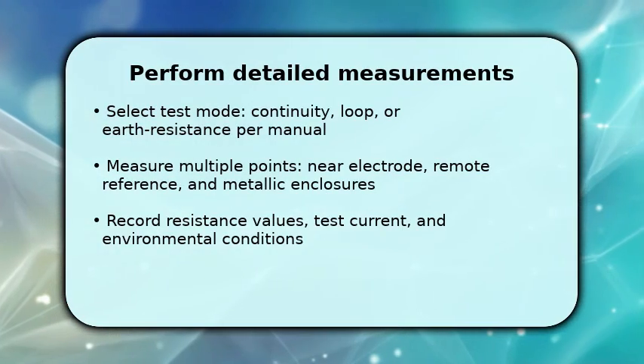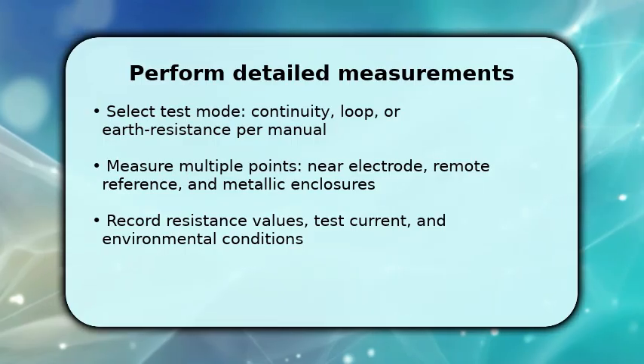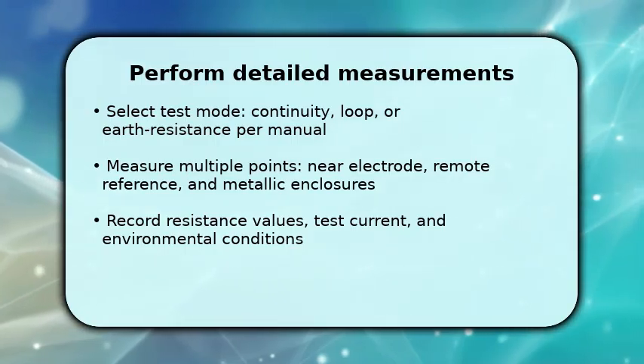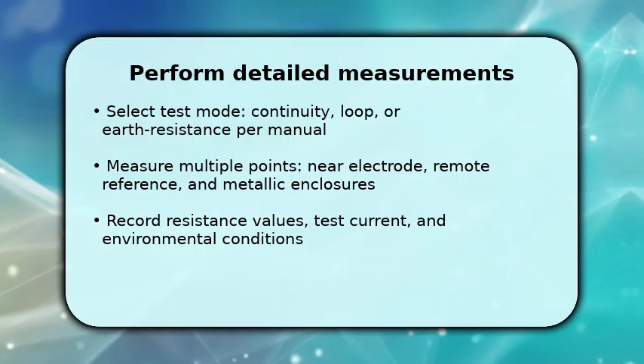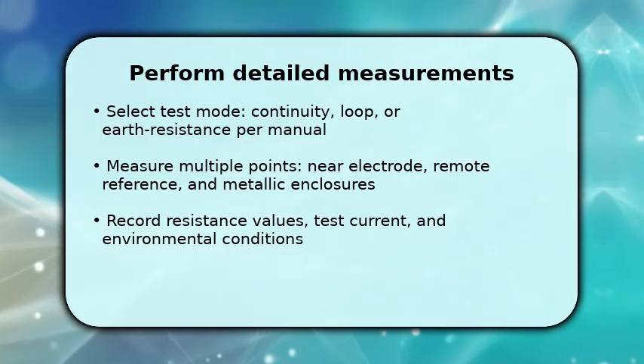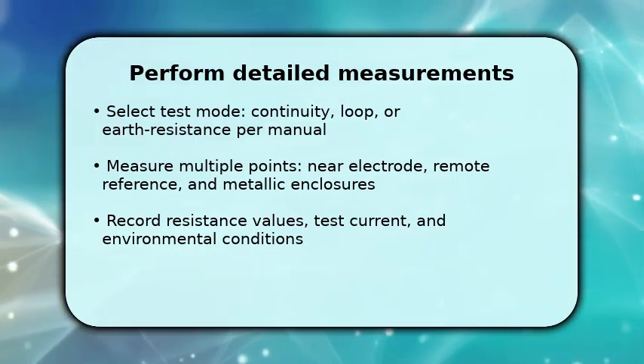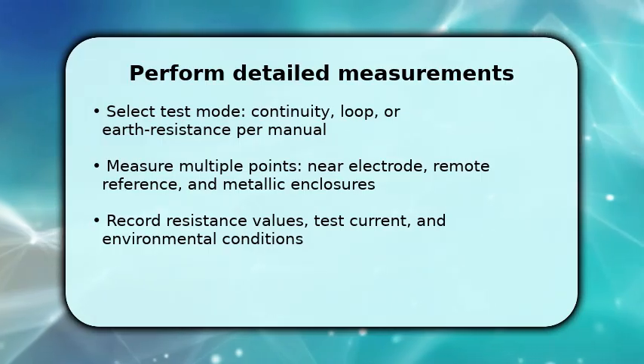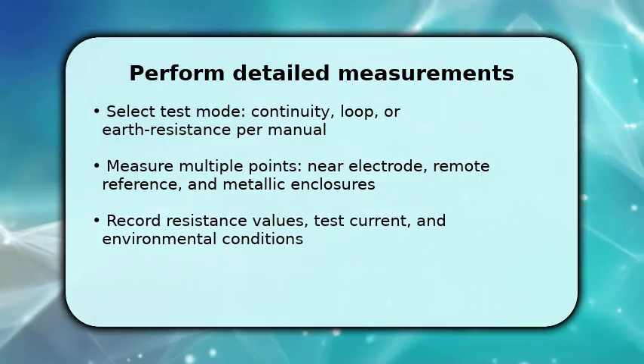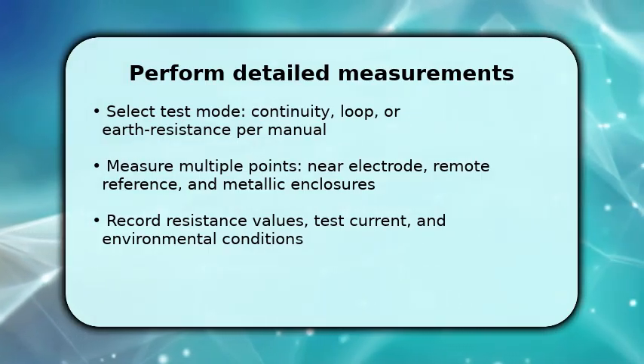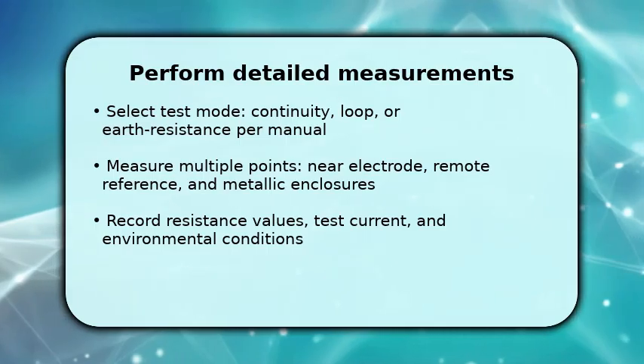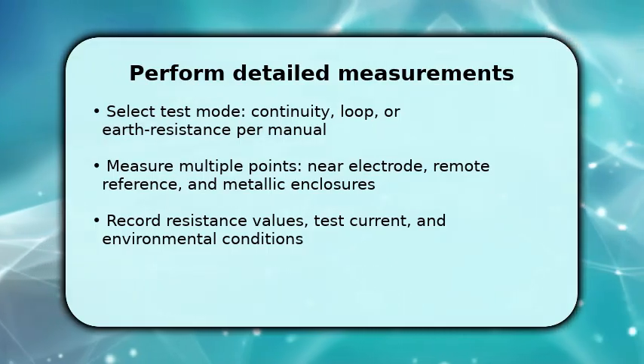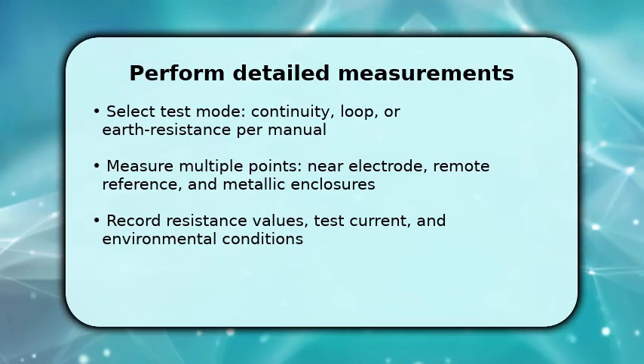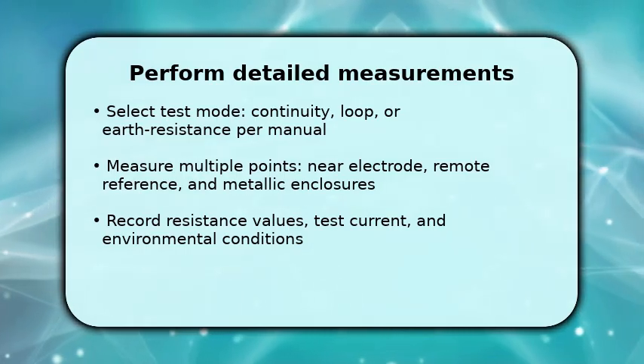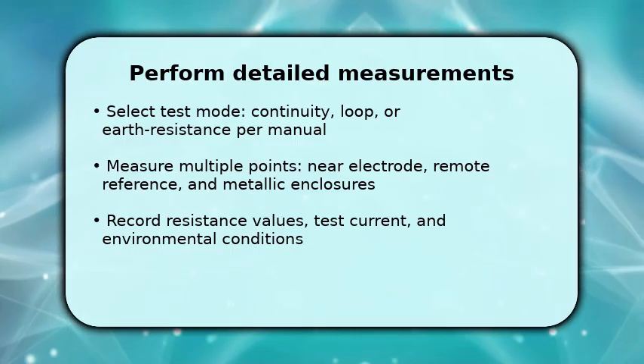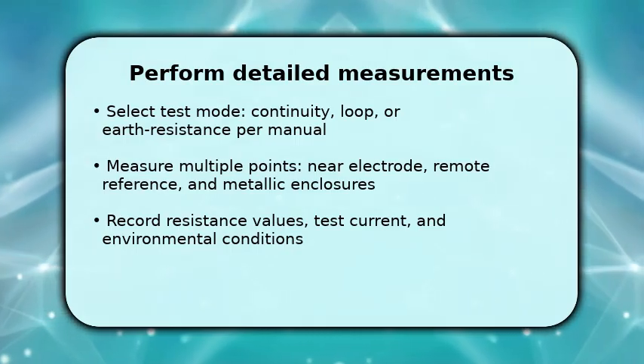You now select the correct mode on the tester based on what you need to verify, whether continuity, loop, or earth resistance. The mode determines test current and interpretation. Next, take measurements at several points, directly at the electrode, at the remote reference probe, and at metallic enclosures connected to earth. Record each resistance reading along with the test current and soil condition so you can compare against standards. Make sure to retest if values fluctuate more than expected.